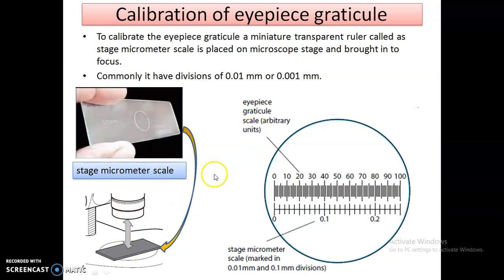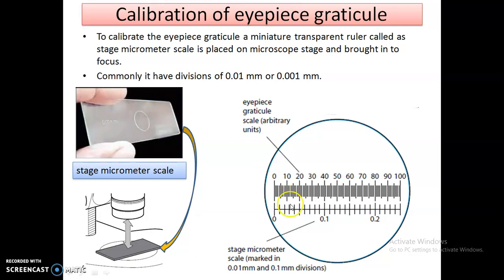When we look through the eyepiece lens, we can see that the eyepiece graticule and the stage micrometer scale lie together in the same field of view. This stage micrometer scale has divisions equal to 0.01 mm or 0.001 mm. As indicated on the miniature transparent ruler shown in the image, the division here equals 0.01 mm. We can see the eyepiece graticule divisions from 0 to 100 alongside the stage micrometer.